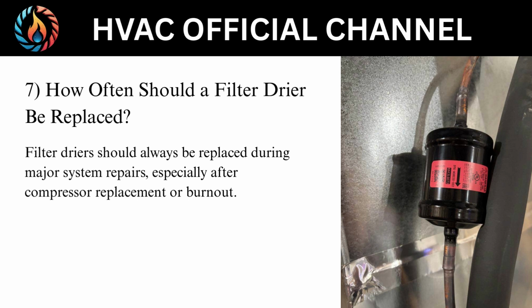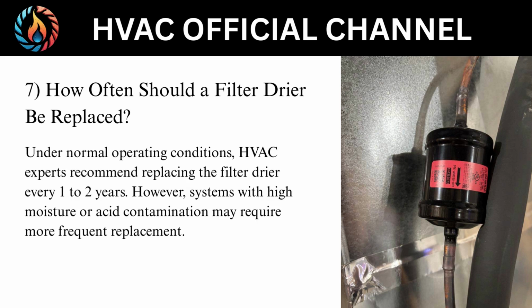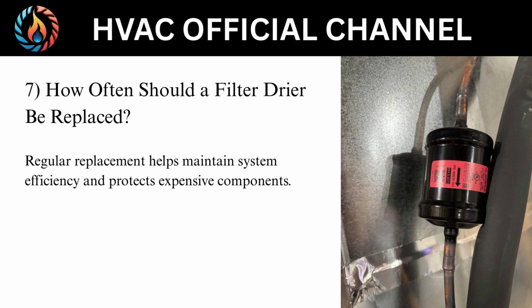7. How often should a filter drier be replaced? Filter driers should always be replaced during major system repairs, especially after compressor replacement or burnout. Under normal operating conditions, HVAC experts recommend replacing the filter drier every 1 to 2 years. However, systems with high moisture or acid contamination may require more frequent replacement. Regular replacement helps maintain system efficiency and protects expensive components.